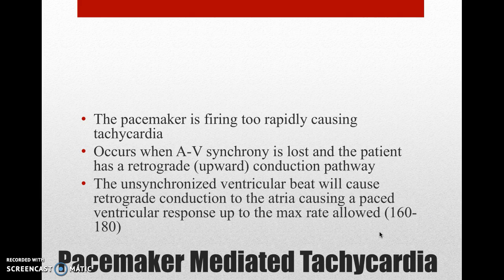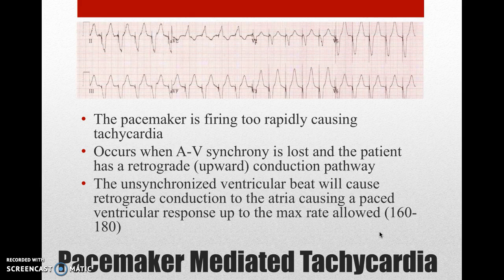Pacemaker-mediated tachycardia is another malfunction that occurs when the pacemaker is firing too rapidly, which causes tachycardia. It occurs when AV synchrony is lost and the patient has a retrograde or upward conduction pathway. The unsynchronized ventricular beat will cause retrograde conduction to the atria, causing a paced ventricular response up to the max rate allowed, around 160 to 180. Note the above strip which shows pacemaker-mediated tachycardia.